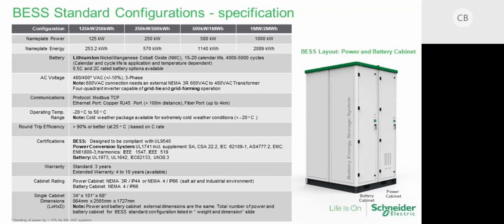And then you see we can scale the system up to 1 megawatt with 2 megawatt hours' worth of battery attached to it. So again, we can provide 1 megawatt for 2 hours. And these lithium-ion batteries, as Mark was mentioning, easily deliver 4,000 to 5,000 cycles. They come in different voltages, typically here in the United States 480 in and out, NEMA 3 rated, so they can sit outside. The system is designed for operating in outside environments from minus 20 C, which, by the way, although I was born in Europe, I'm not quite sure what minus 20 C is in Fahrenheit, to 50 C Celsius. So you see all the different kinds of things.